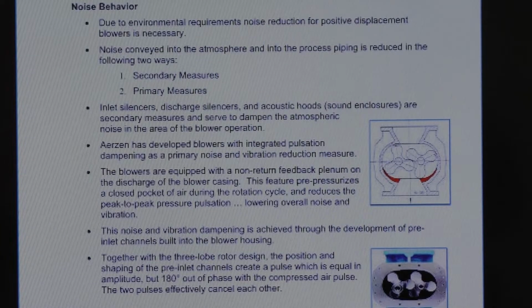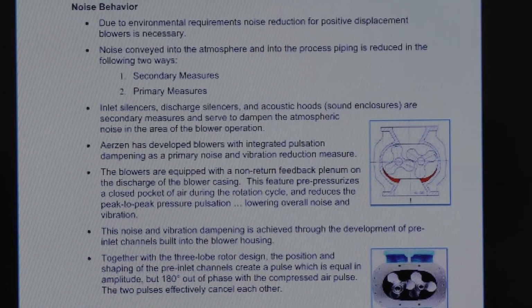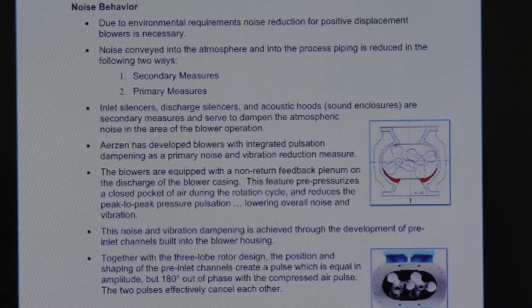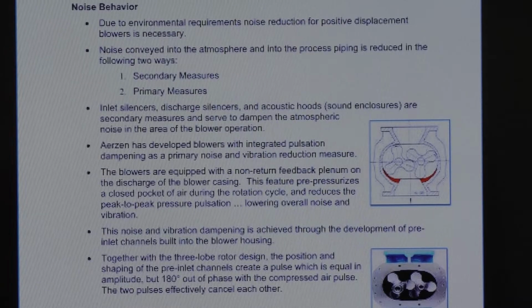Because in our blowers, if you were to just turn the blower on to an open pipe, it'll never build pressure. It just moves air. What creates the pressure on the unit is whatever's in the system that it is operating in. Go ahead and go to the next one.